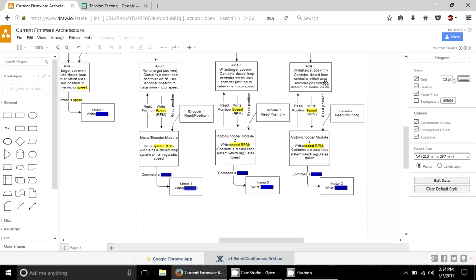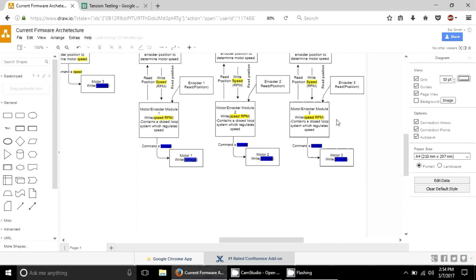What's different is we've added this extra module in here. So this closed-loop controller based on position is commanding a speed. This is a second closed-loop controller, but instead of being based on position, this one is based on speed - continuously measuring the motor's speed and applying a voltage to correct it. What this module does is correct for any changes in torque experienced by the motor.